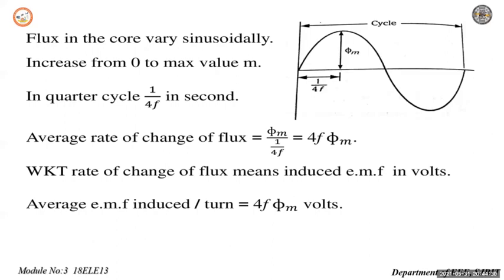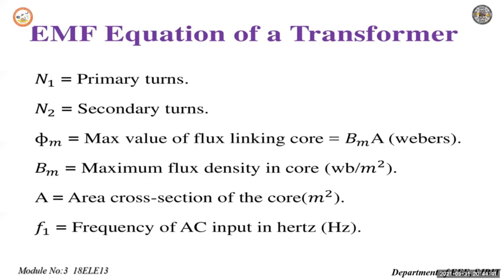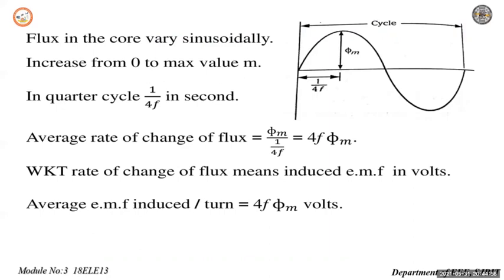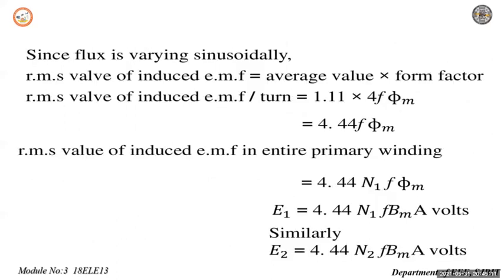The quantities which affect the magnitude of the induced EMF are phi, phi m, N1 and N2, where phi is the flux, N1 is the number of primary turns, and the number of secondary turns is N2. E1 is the RMS value of the primary induced EMF, and E2 is the RMS value of the secondary induced EMF. Now, from Faraday's laws of electromagnetic induction, the average EMF induced in each turn is proportional to the average rate of change of flux. Average EMF per turn is nothing but d phi by dt. If you derive it, you will arrive at the relations E1 equals 4.44 f phi m N1 and E2 equals 4.44 f phi m N2, expressed in terms of phi m.